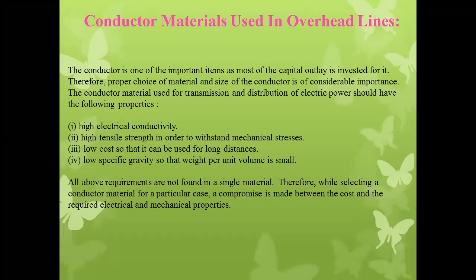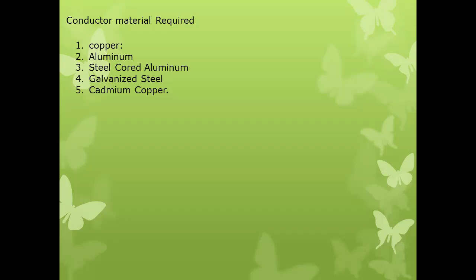Okay, so some important conductor materials are copper, aluminium, steel cored aluminium, galvanized steel, and cadmium copper. Copper is a good conductor of electrical energy, but the tensile strength of copper is a little lesser than that of steel cored aluminium. Also, the specific gravity of copper is more than that of aluminium, so the weight of the line conductors will increase, and it will affect the sag of the overhead transmission line and also the cross arm life. So aluminium, steel cored aluminium, galvanized steel, and cadmium copper are generally used as conductor material.